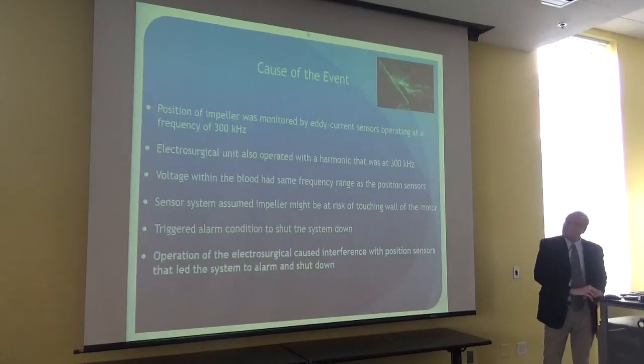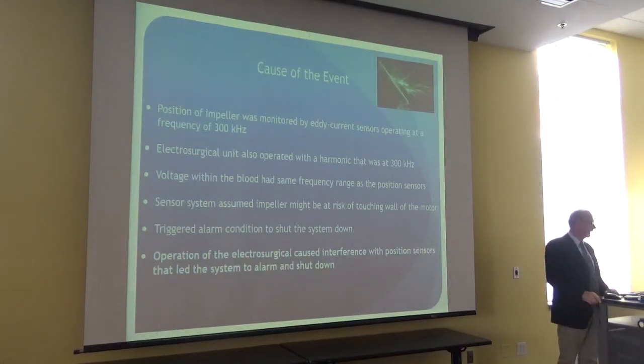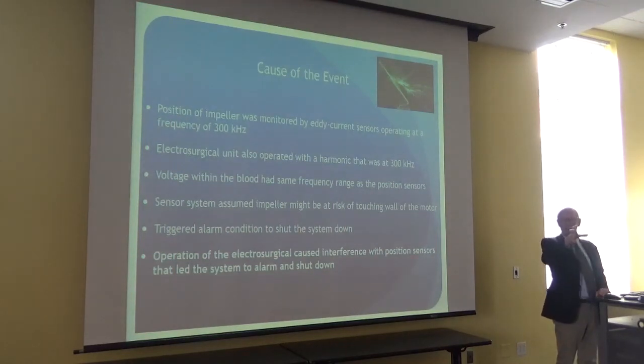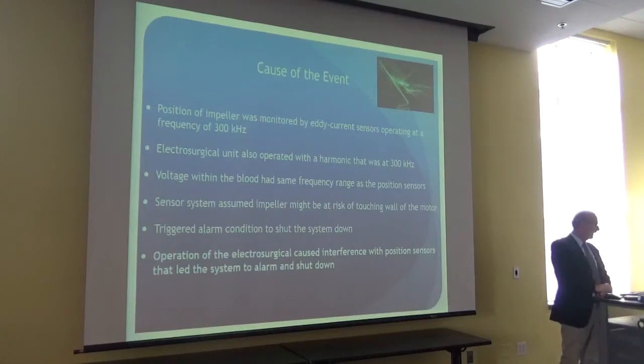And so the impeller was being monitored by these eddy current sensors, and they were operating at about 300 kilohertz frequency. The interesting thing is that when they turned the electrical surgery unit on, it also operated with a harmonic of 300 kilohertz. And moreover, when they turned it on, because they were contacting the body, that voltage actually was transmitted right through the blood to the pump, into the motor, and up to the controller to say something's going on here. And so the sensor system assumed the impeller might be at risk of making contact with the motor.